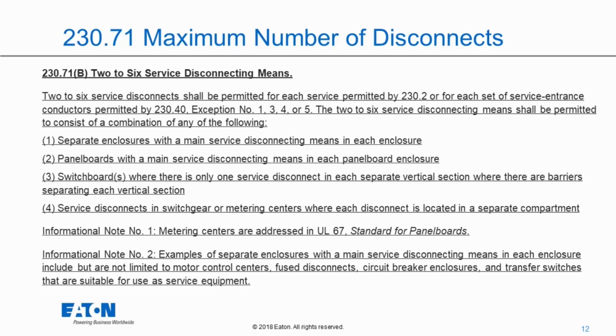The real drive for that was all about arc flash hazards and accidental shock, and being able to work on that equipment. It is very common that you'd have to go into that service equipment and work on load terminations, and in many cases you cannot de-energize. So that adds an additional amount of protection.